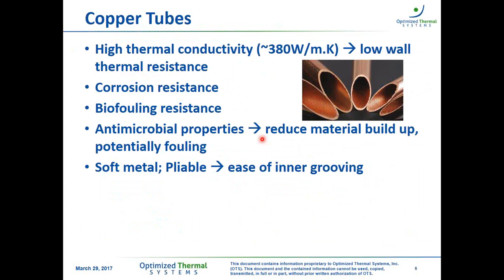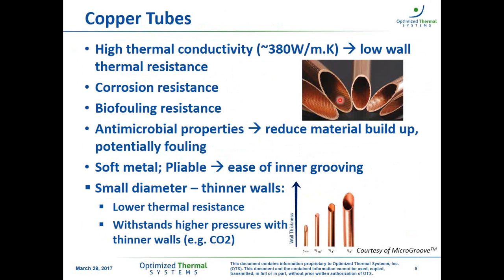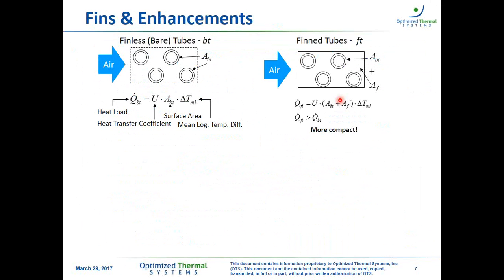In addition to that, copper tubes are a soft metal, pliable, so there's ease of inner grooving. Inner grooving, I mean those grooves indicated by the image here on the upper right corner. Now, if we combine copper tubes with small diameters, we have some further advantages. Small diameters, we will end up with thinner walls. Thinner walls mean an even lower thermal resistance because we're reducing the distance between inner and outer fluid. And the second one, in particular for high pressure systems such as CO2, small diameter tubes with thinner walls can withstand those high pressures using less material than conventional diameter tube heat exchangers. Now, let's just briefly introduce fins and enhancements, and why do we have fins?